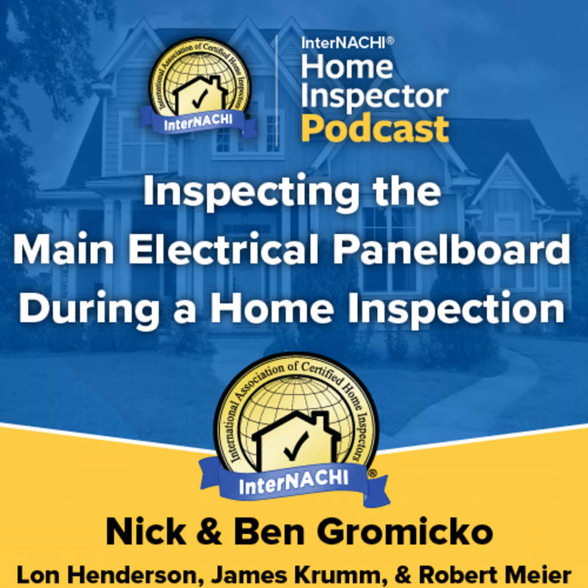Illumination. Artificial illumination must be provided for the panel board working space. Dead front. The door or cover of the panel board cabinet is called the dead front. The dead front of a panel board cabinet protects a person from live parts within the panel board. According to the InterNACHI Home Inspection Standards of Practice, the home inspector is not required to remove the panel board cabinet cover or dead front.